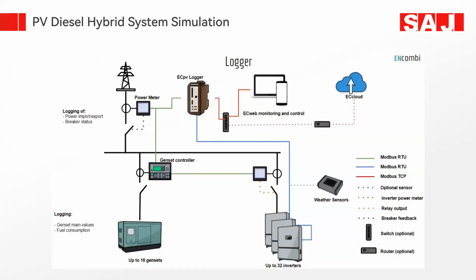Now we will talk about the PV diesel hybrid system simulations. The main concern of the customer in the commercial series is that every customer wants the genset controller system. In our commercial C6 series, we have provided a few vendors our Modbus protocols for the PV diesel genset controller synchronization. How will it work? It will work like this.